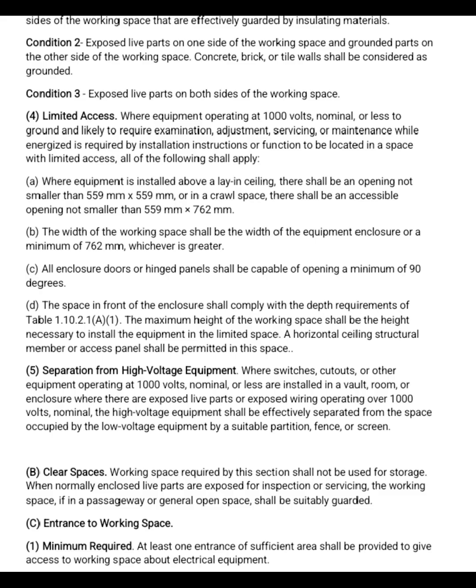A. Where equipment is installed above a lay-in ceiling, there shall be an opening not smaller than 559 mm times 559 mm, or in a crawl space, there shall be an accessible opening not smaller than 559 mm times 762 mm. B. The width of the working space shall be the width of the equipment enclosure or a minimum of 762 mm, whichever is greater.